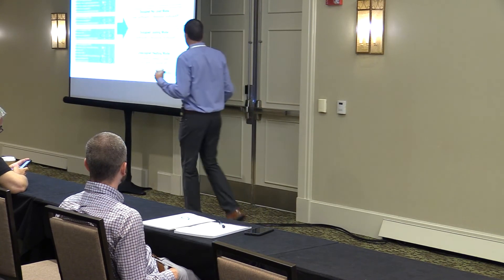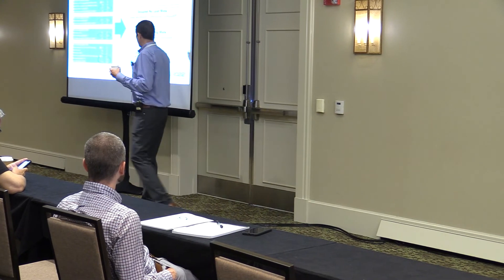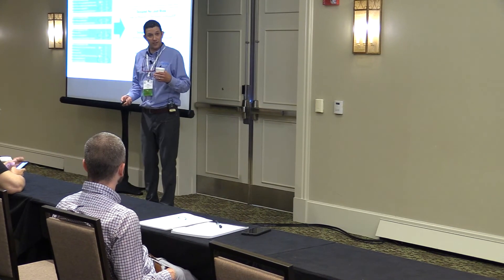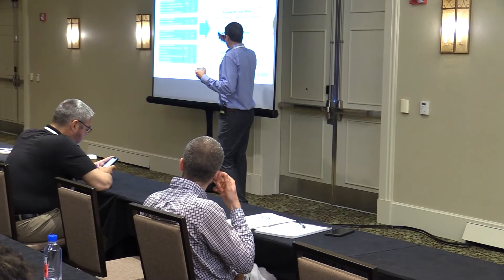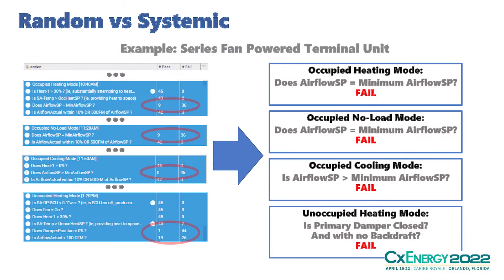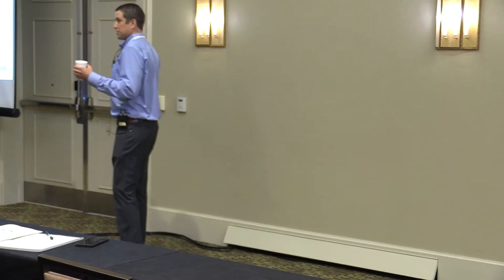In this example — whenever there was a call for airflow, it always went to max, never to minimum or heating mode. That was a systemic problem easily visible in the bulk results. Then reporting — can you automate reporting? That would be fantastic, and it's all possible with technology.